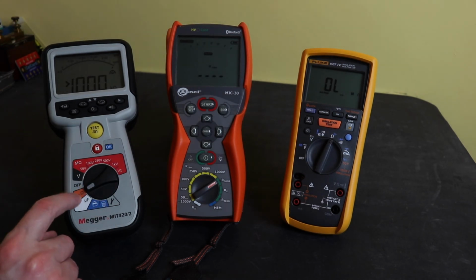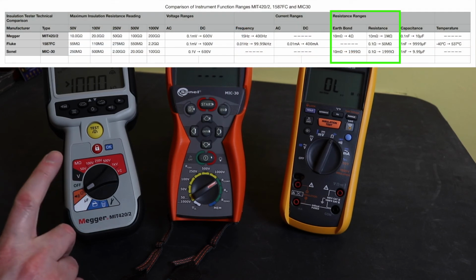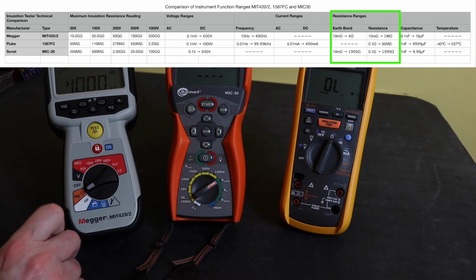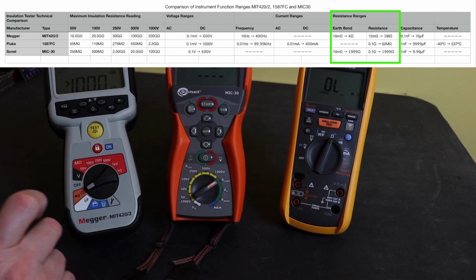These other two instruments work slightly differently. Ohms and continuity are all on the same test function. For the Megger here, it is also 200 milliamps. The Megger here will measure from 10 milliohms up to 1 megaohms, fully automatic. The 200 milliamp test current will drop as the resistance increases.